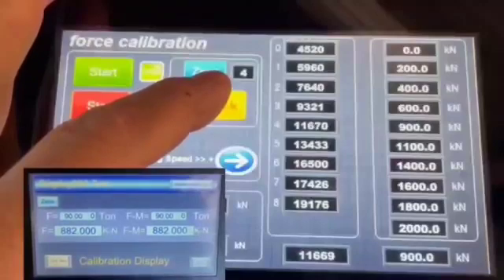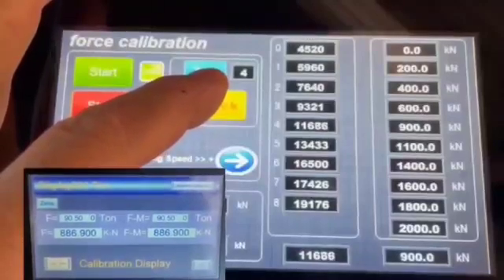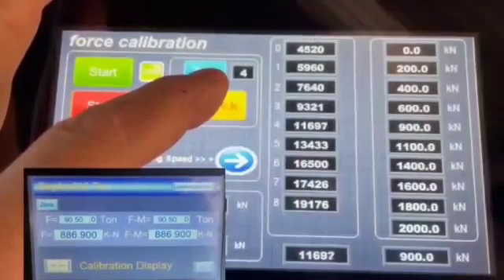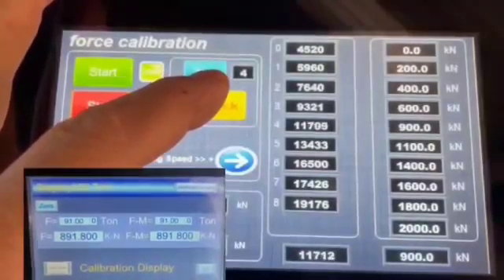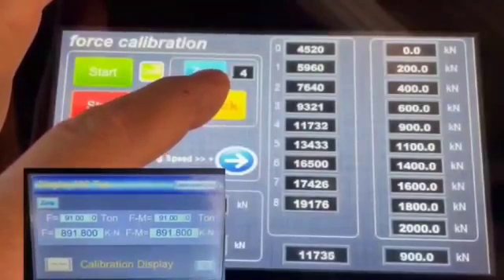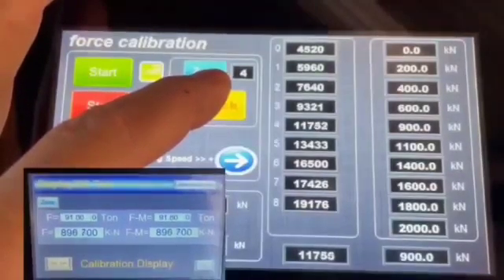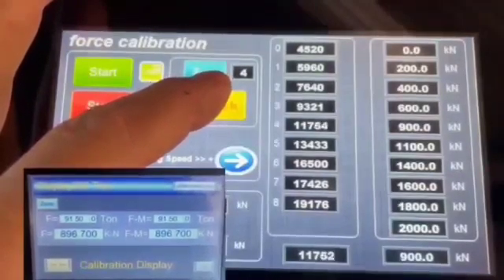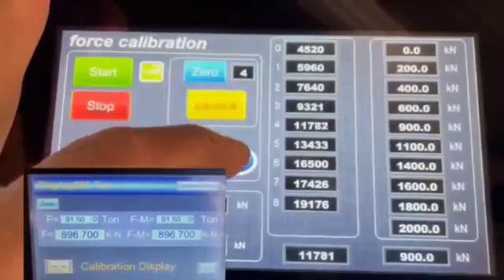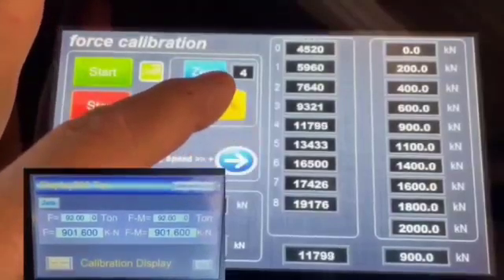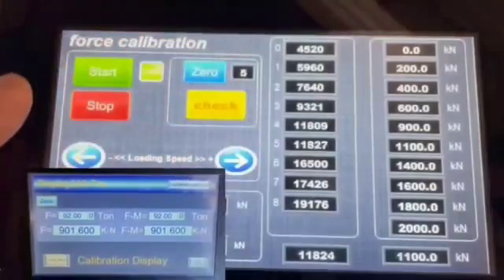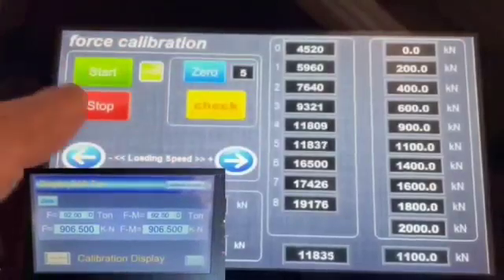On the left side of the 900, the number is changing. Now I'm close to 900. Whenever I hit the number 900 on the load cell display, I'm going to push the check button on the compression display to set that pressure for the force.